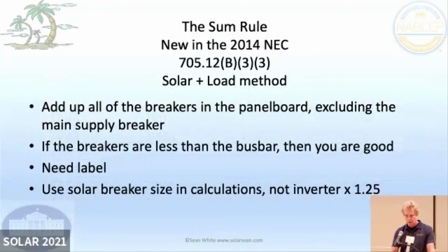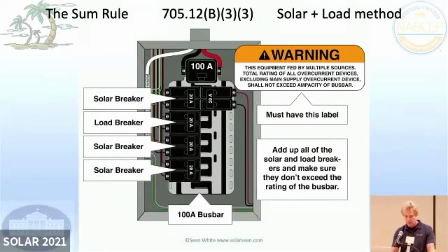This one is called the sum rule. I call it the sum rule, but some people call it the solar plus the load breaker rule. And what was put here before is we were penalized by the 120% rule a lot of times. And that was if we were just combining inverters. So let's say I had a 100 amp sub panel, I should be able to put 100 amps of inverters there and combine them together, because I'm never going to send more than 100 amps back. And you couldn't do that with the 120% rule.